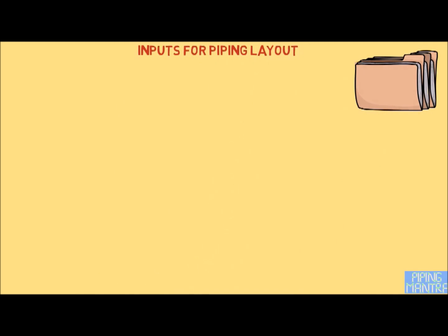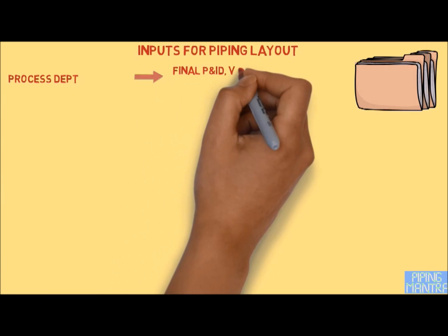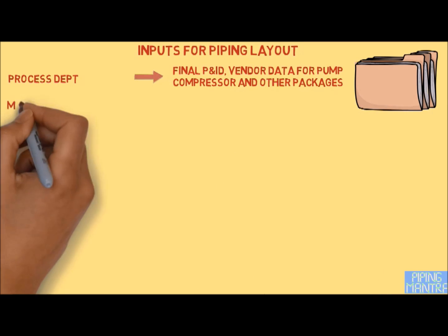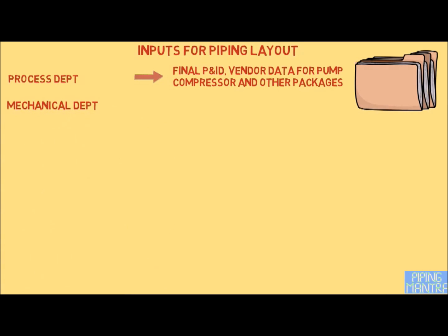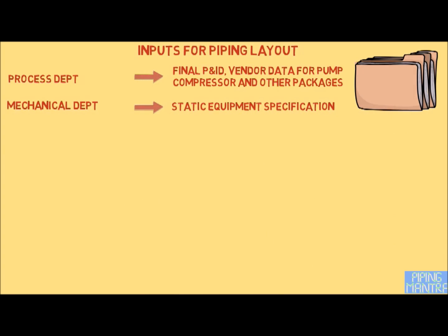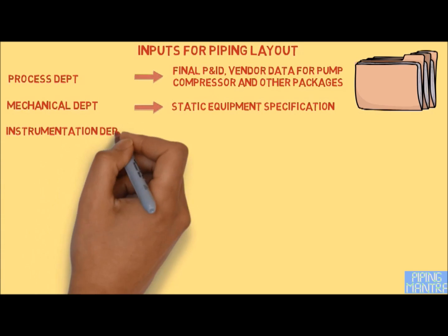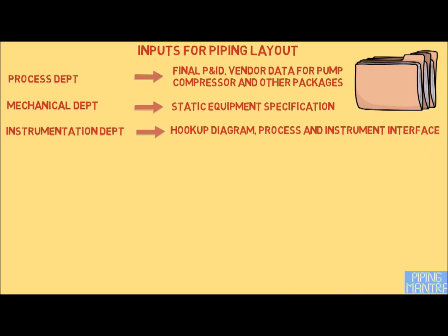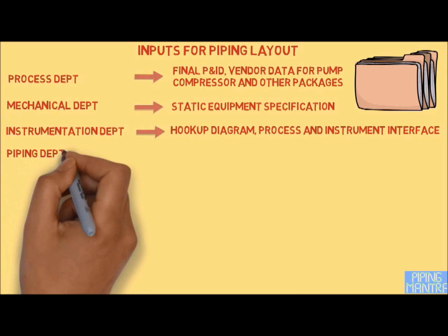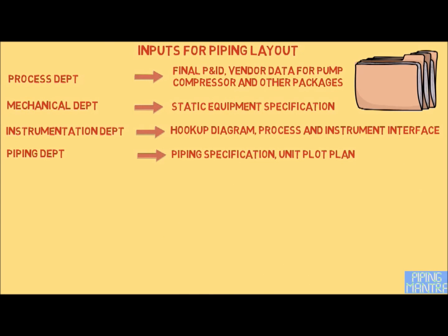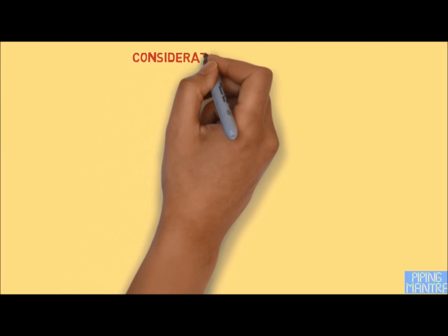The final piping plan can be issued for construction. For preparing this piping layout we need inputs from other disciplines: from the process group we need final P&ID; from the mechanical department we need vendor data for pumps, compressors, and other packages, and static equipment specifications for vessels and tanks; from instrumentation and control systems we need hookup diagrams and process-instrument interfaces; and from the piping department we need piping specifications and the unit plot plan.